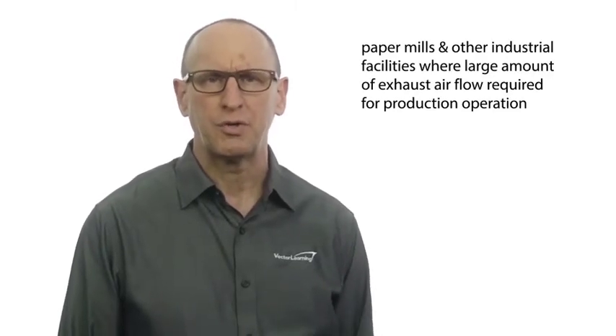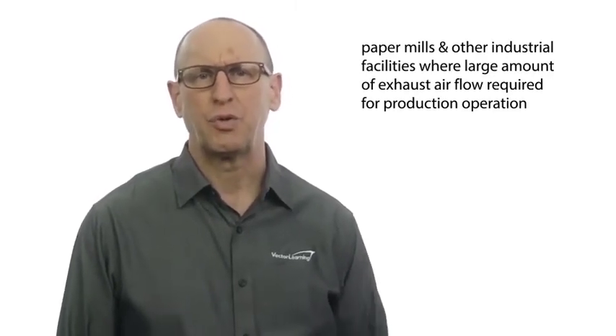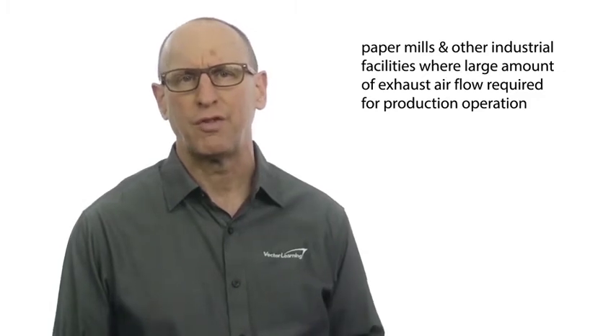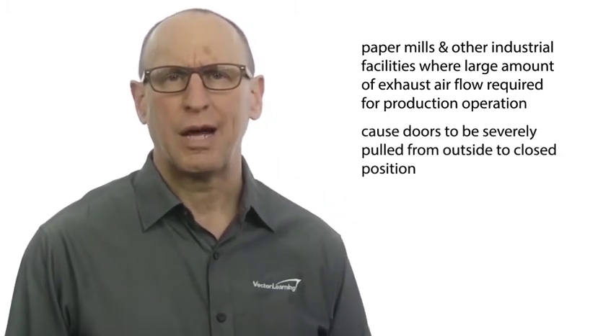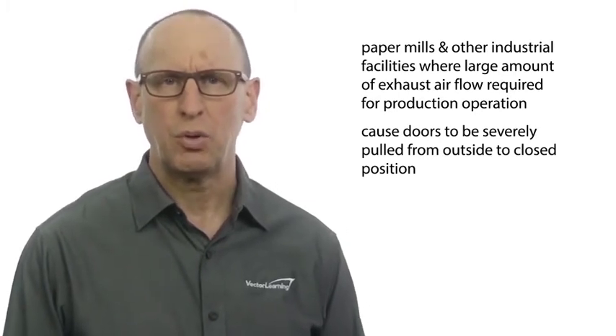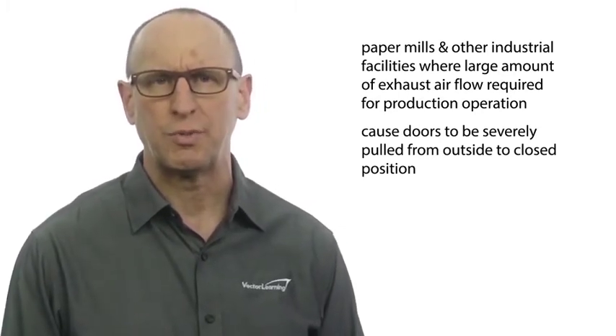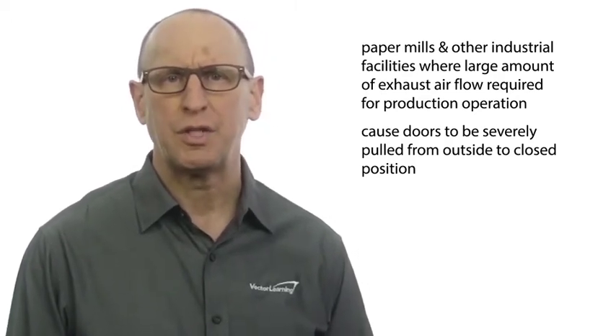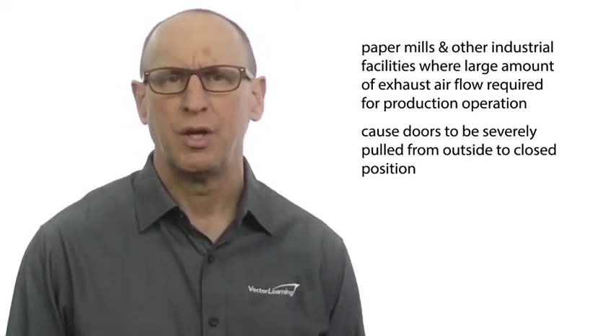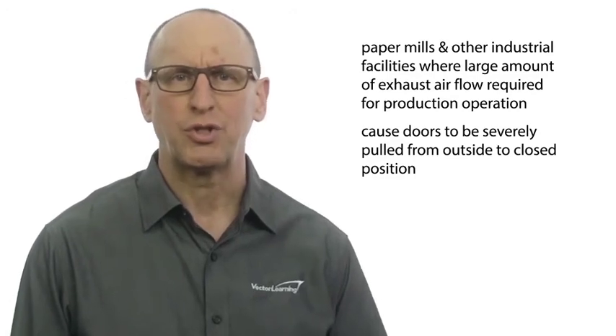Some facilities need to pay special attention to this condition, such as, from my experience, in paper mills and other industrial facilities where there's a large amount of exhaust air flow required for the production operation. This can cause outside doors to be severely pulled from the outside to a closed position. One solution I used was to add makeup air to the facility to try to equalize the pressure and avoid the huge negative pressure in the building.